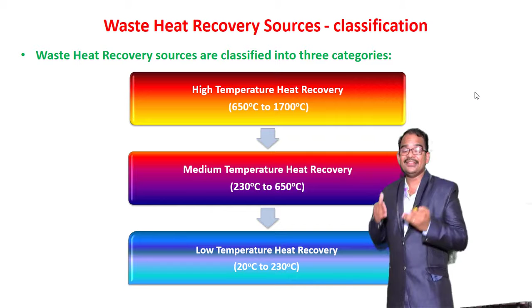So we have three different classifications. The first is low temperature heat recovery, with temperatures between 20 degrees centigrade and 230 degrees centigrade. The second is medium temperature heat recovery, with temperatures between 230 degrees centigrade and 650 degrees centigrade. And the last is high temperature heat recovery, where the temperatures range between 650 degrees centigrade and 1700 degrees centigrade or even higher. So this is the waste heat recovery classification.